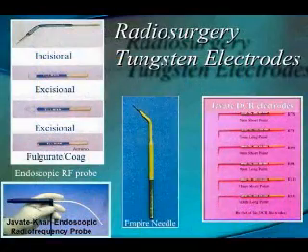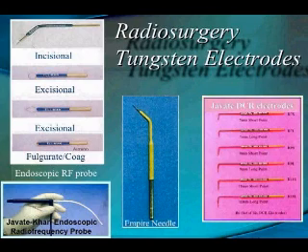There are many types of electrodes developed for radiofrequency units. The fine wire electrodes, for extremely fine excisions and incisions. The round loop electrodes for looping off small eyelid neoplasms and obtaining biopsy specimens from bigger size neoplasms. The triangular or oval loop electrodes used for excision of raised and pedunculated skin lesions. The ball electrodes for coagulation.